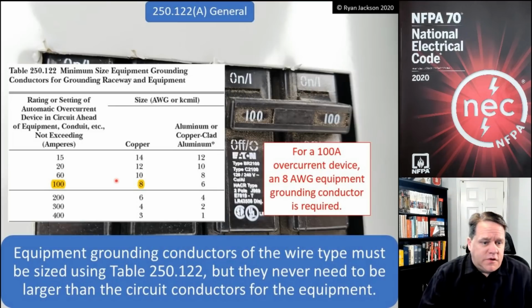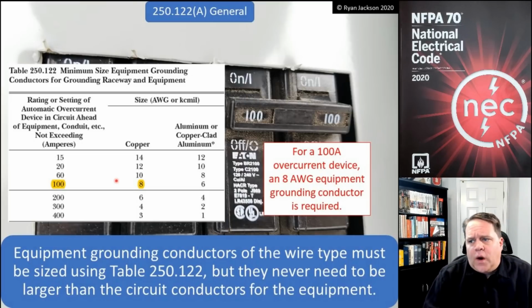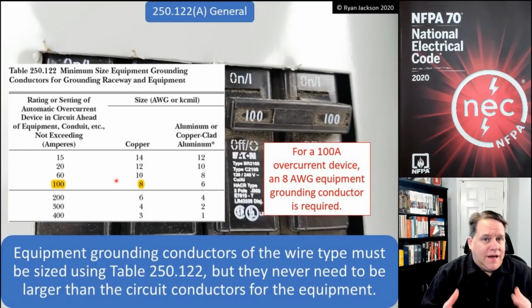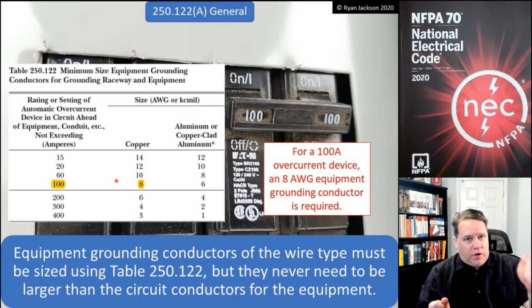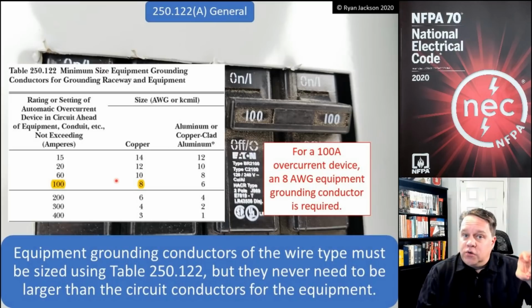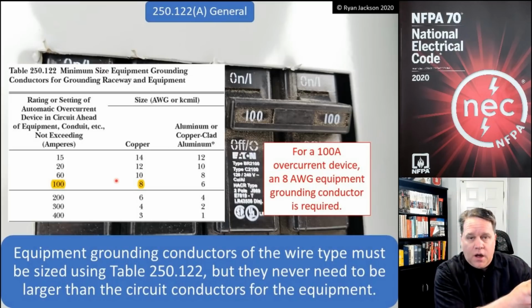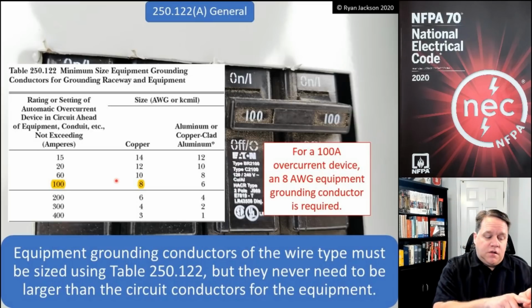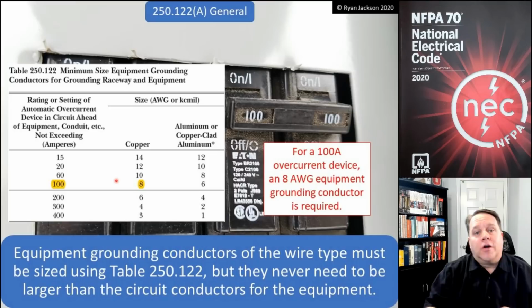So we size the equipment grounding conductor based off the rating of the circuit breaker or fuse that it needs to open. So when we think about sizing it, we need to understand why we install an equipment grounding conductor. Why do you put a green wire inside of your PVC conduit, for example, or inside of your MC cable? And the answer to that is to open a fuse or breaker in the event of a ground fault.